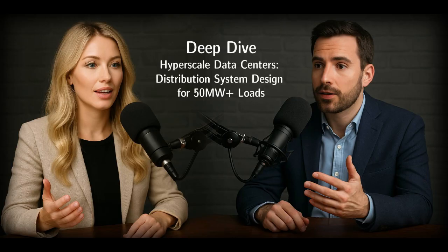Let's use a big example, say a 100 megawatt data center. What's the 69 kilovolt design look like? Okay, 100 megawatts at 69 kilovolt, 0.95 power factor again. The current is about 881 ampere.